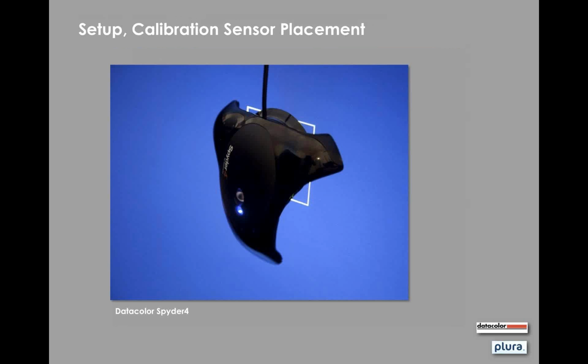Once they're connected, you will see a white target square on the reference display. You place the Spyder over that, and you can see that I'm overlapping the square. There's a rubber gasket that goes around the sensor port on the Spyder, so I'm not missing the edges of the square by much. It probably could come down 1/4 of an inch, but as a practical matter, it makes no difference.